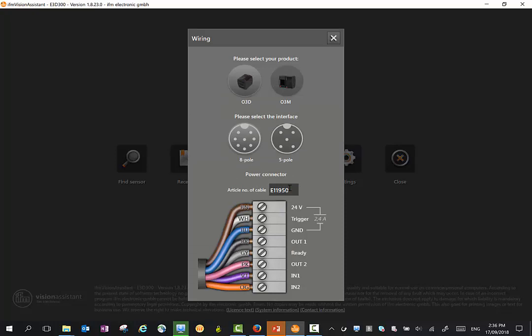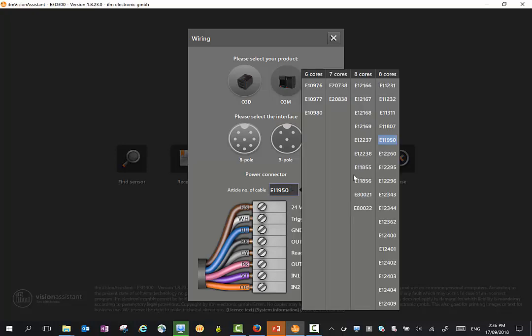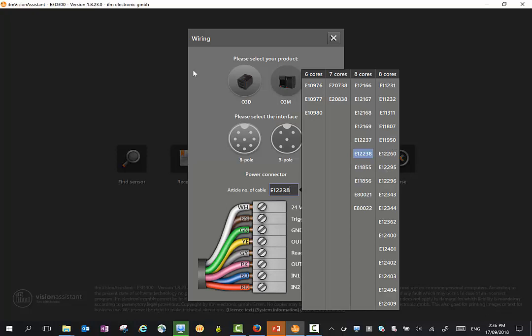The wiring diagram includes different cables here as well. So if you've got different IFM cables, you can pick them and you will see the color scheme change. Because 8-core cables have two different wiring schemes, if you pick the wrong one, the sensor may work but not correctly. Best to do this step first and get the wiring correct.